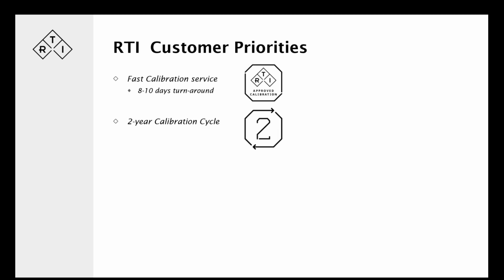But that's very appreciated. Also appreciated is the 2-year calibration cycle. That's what we recommend. Of course, it's the customer who makes the decision about the calibration cycle, but our recommendation is once every 2 years. We're happy to do it every year if you like, or twice a year, but our recommendation is still once every 2 years. That's good enough for us.